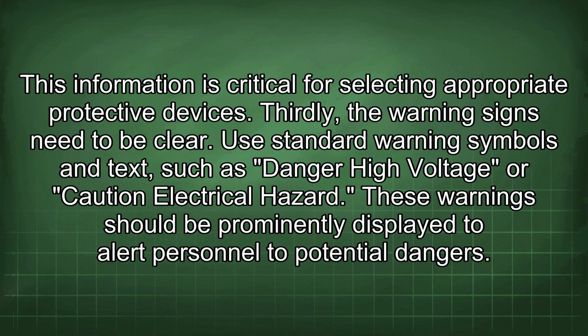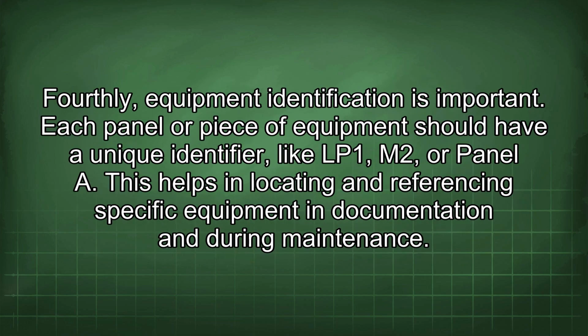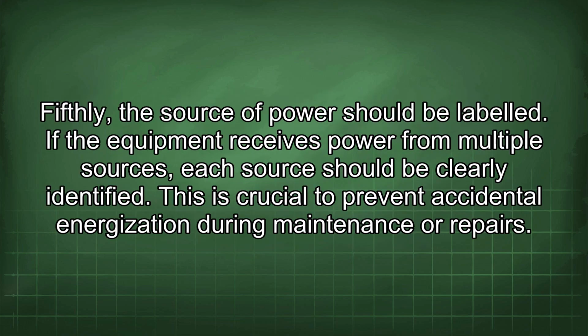Thirdly, the warning signs need to be clear. Use standard warning symbols and text, such as danger, high voltage, or caution, electrical hazard. These warnings should be prominently displayed to alert personnel to potential dangers. Fourthly, equipment identification is important. Each panel or piece of equipment should have a unique identifier, like LP1, M2, or Panel A. This helps in locating and referencing specific equipment in documentation and during maintenance. Fifthly, the source of power should be labeled. If the equipment receives power from multiple sources, each source should be clearly identified. This is crucial to prevent accidental energization during maintenance or repairs.